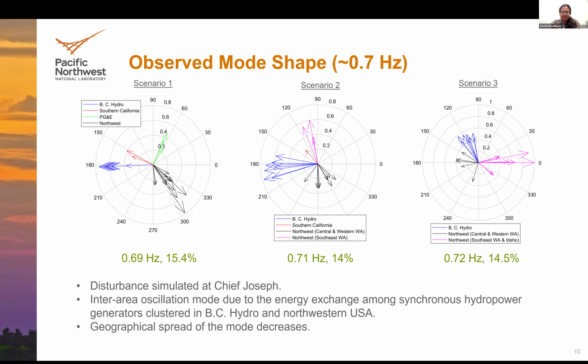But this study has a lot of limitations. For example, we were not changing the power flow case, but as more solar goes up in California, how the power flow looks like today is not going to look the same. We also assume that whatever generator we were replacing, the amount of generator injection is not going to change with inverters, but realistically that is not going to be the case. So although this model-based study gives us an indication of what might happen, it is limited because we cannot simulate all possible scenarios and all possible heterogeneous fleets of inverters that might show up.